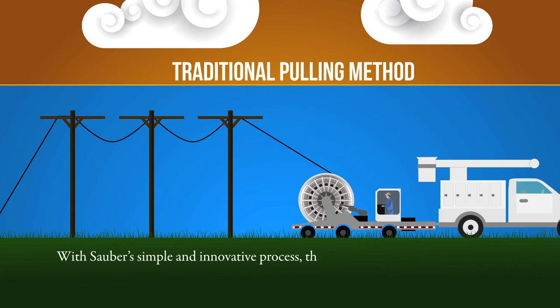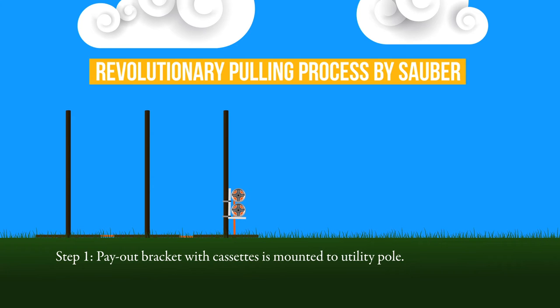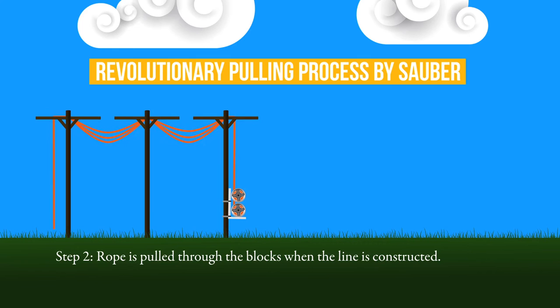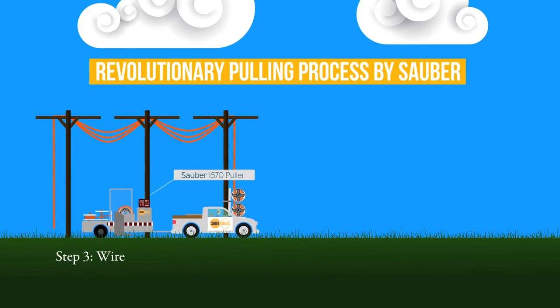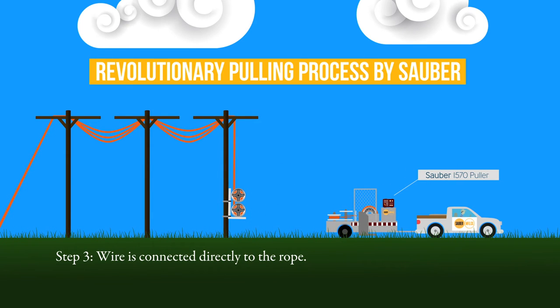With Sauber's simple and innovative process, the P-line is no longer needed at all, saving crew time. Begin the process by mounting the payout bracket with cassettes of 5/16th rope to the utility pole. The rope is then pulled through the blocks when the line is constructed. The wire is connected directly to the rope, which has a 13,700-pound breaking strength.